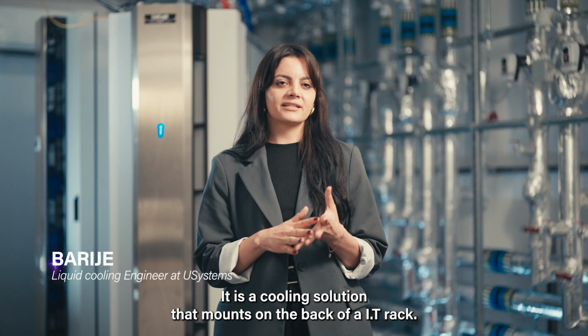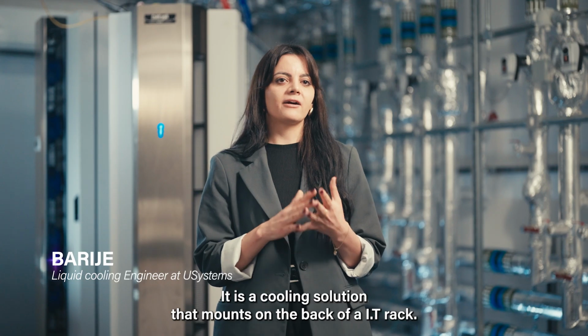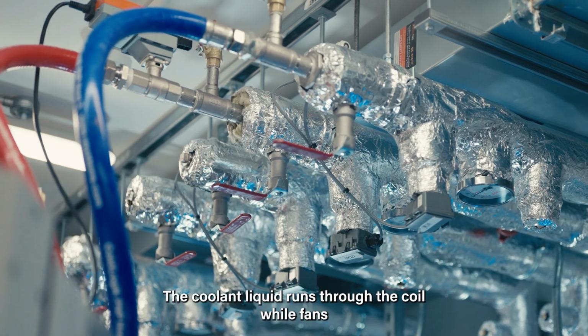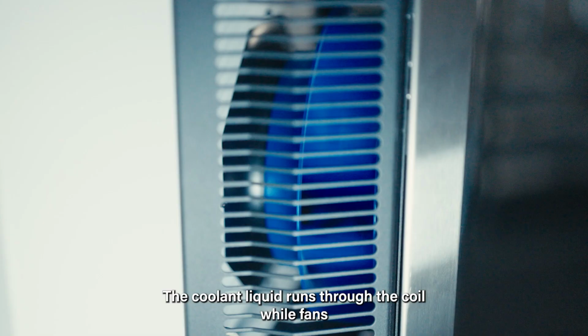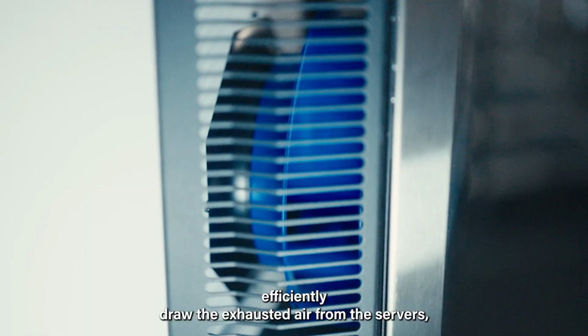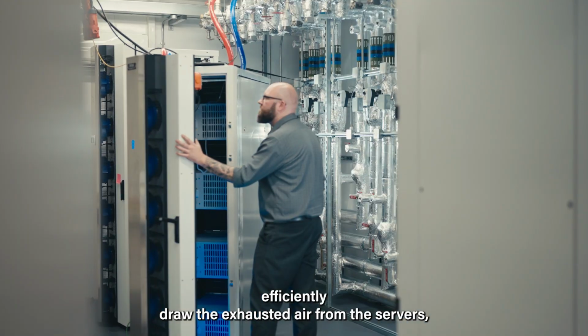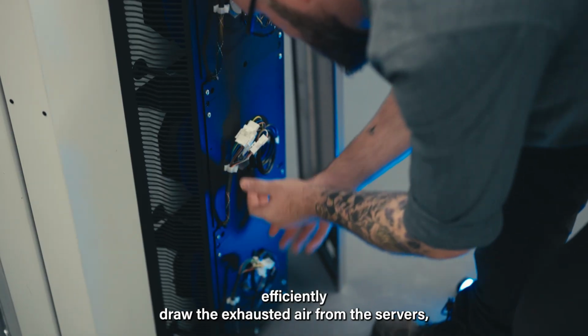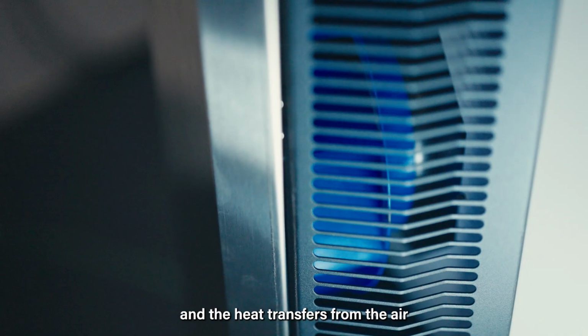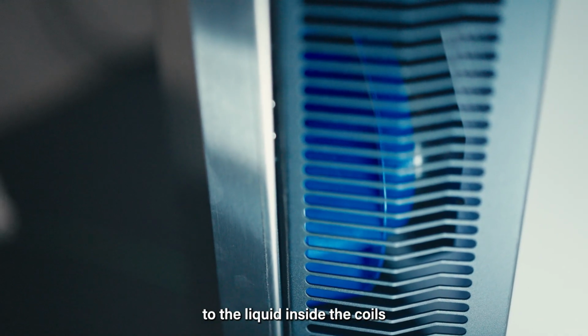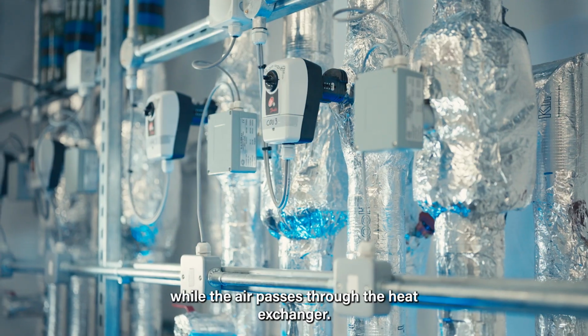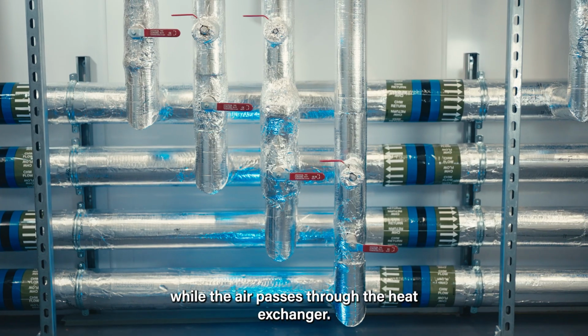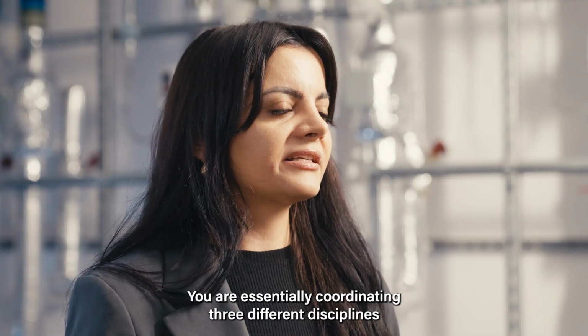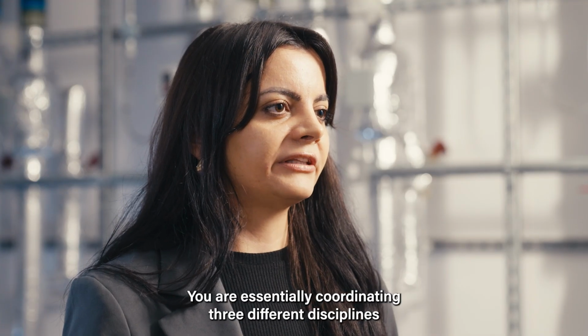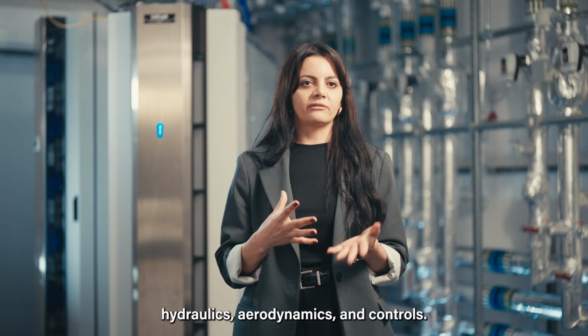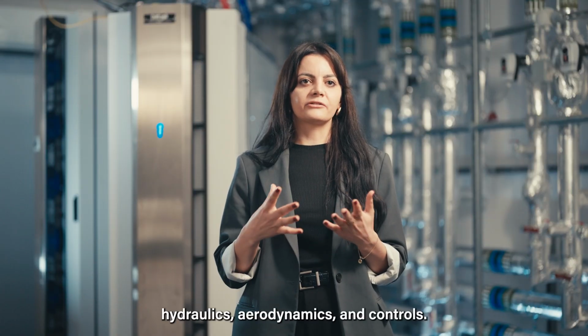It is a cooling solution that mounts on the back of an IT rack. The coolant liquid runs through the coil while fans efficiently draw the exhausted air from the servers, and the heat transfers from the air to the liquid inside the coils as the air passes through the heat exchanger. You are essentially coordinating three different disciplines: hydraulics, aerodynamics, and controls.